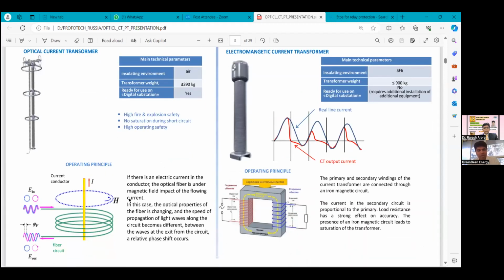Before that, let me give an idea about the working principle of this optical CT. Here, current passes through the conductor, and the light passes through the optical winding, and the phase shift that occurs is determined as the current measured. In case the optical properties of the fiber change, the speed of propagation of the light wave along the circuit becomes different between the waves at the exit from the circuit, and a relative phase shift occurs. This phase shift is considered as the current measured.